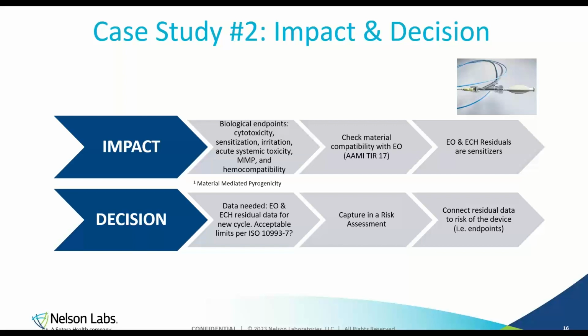So in my decision line, I really want to see the EO and ECH residual data for the new cycle. And I want to make sure that that data shows acceptable limits for ISO 10993 Part 7. So this is an interesting point where sterilization and biocompatibility overlap. So for EO sterilization, we have a residuals document that resides with the biocompatibility expert working group, because we have the toxicologists to assess whether those chemicals would be toxic to patients based on device use and patient population.